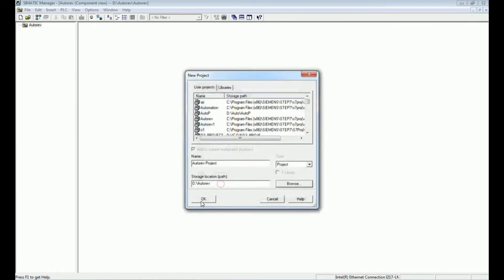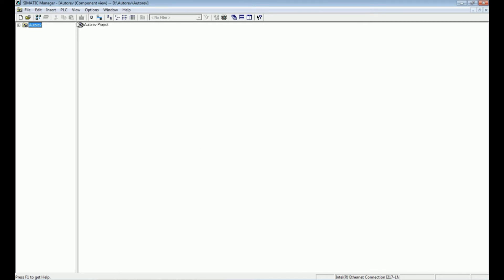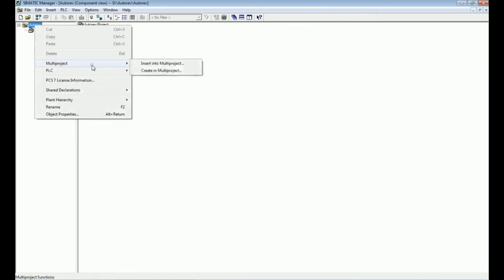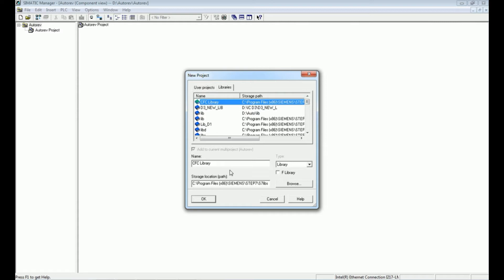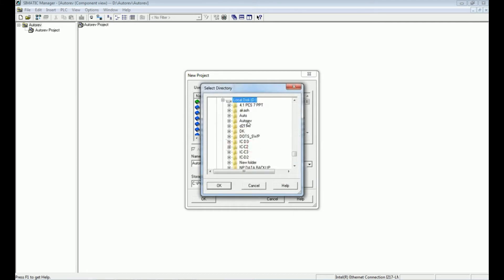We have successfully created the project. In this project we will define a library. Right-click on the multi-project, go to 'Create in Multi Project', and here we will define the library. The library gives us default programming blocks — when going for logical operations we can use function blocks, SFC, or CFC from this library. Siemens also provides default libraries such as the CFC library and PCS 7 AP libraries. Now I will create a new library and give it a name — 'Total Library' — and assign the same path.